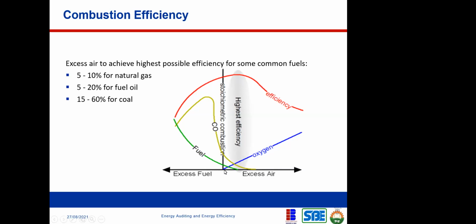Now, if you look at this diagram here, the horizontal axis is excess air, and if you take it to the left, you're going to see excess fuel, right? So the point where you have complete combustion, where you have the highest efficiency, is at this point. Okay, you see the red line, which is the efficiency. This is just a plot trying to correlate the impact of oxygen and fuel to the efficiency level of your combustion. The green line is the fuel, while the blue line is the oxygen. So if you look at the point where you have the highest efficiency, you find out that the oxygen and the fuel are almost, I mean, they're in close proximity.